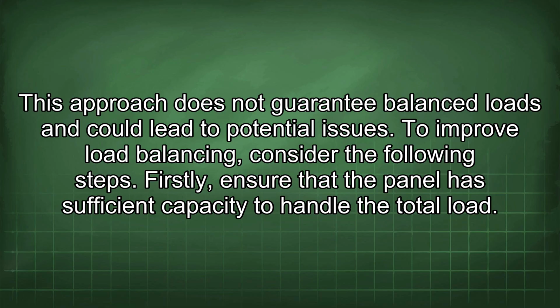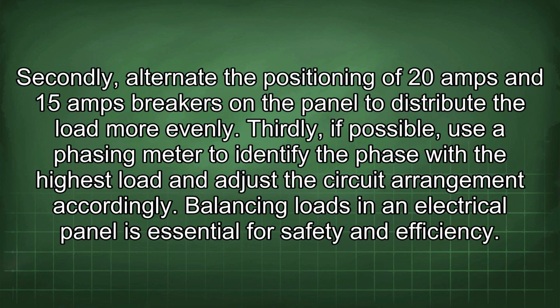To improve load balancing, consider the following steps. Firstly, ensure that the panel has sufficient capacity to handle the total load. Secondly, alternate the positioning of 20 amps and 15 amps breakers on the panel to distribute the load more evenly. Thirdly, if possible, use a phasing meter to identify the phase with the highest load and adjust the circuit arrangement accordingly. Balancing loads in an electrical panel is essential for safety and efficiency.